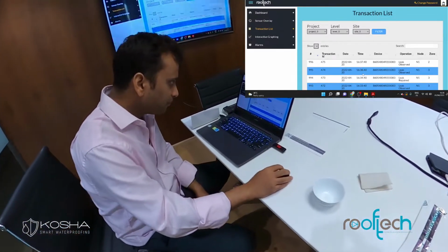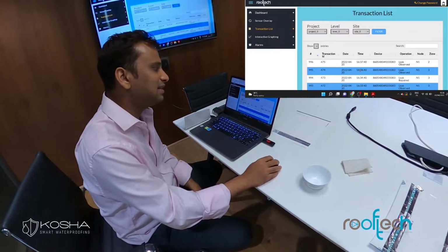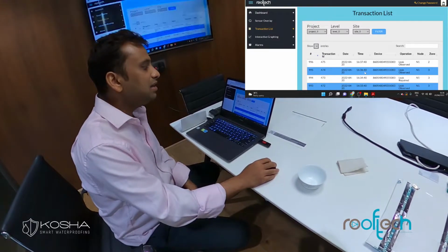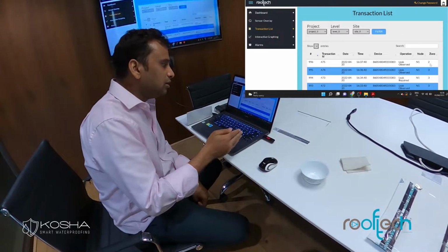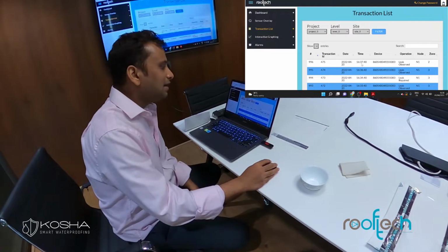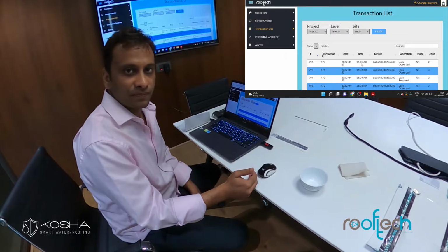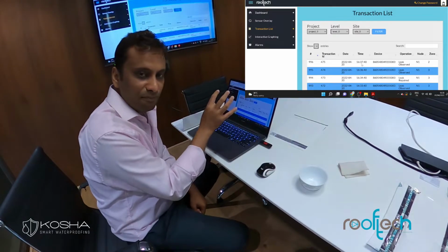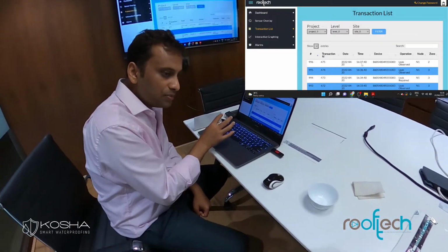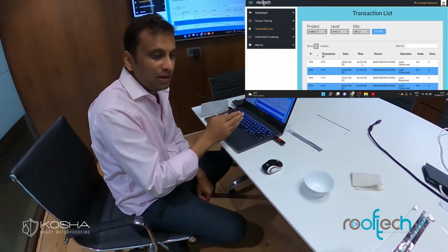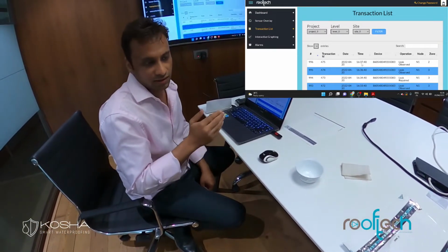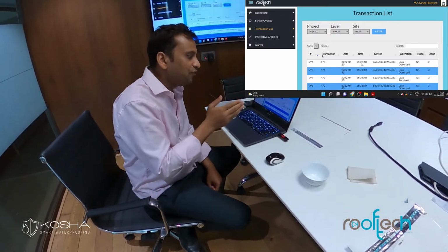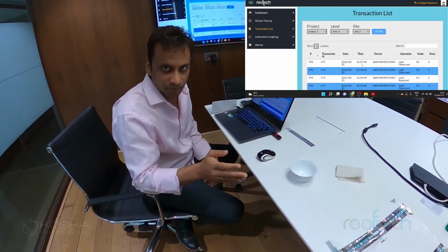We now know that at 16:36 zone number 3 started leaking, and eventually the water spread to zone number 2 and it started leaking at 16:37. So my software understands and analyzes the pattern of leakage observed and tells you the probability, or with short information, that you should actually look at zone number 3 and you should find that leaking problem.